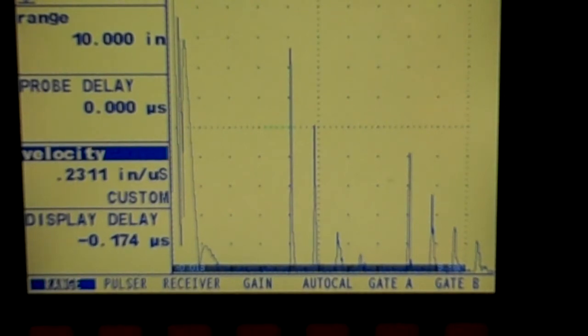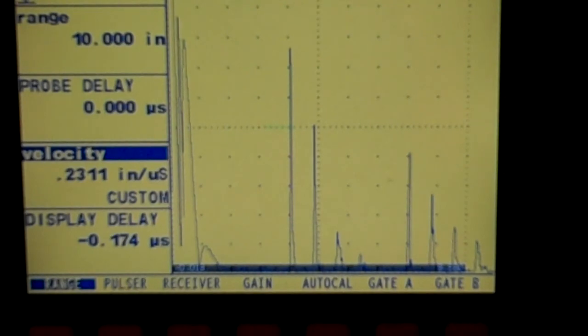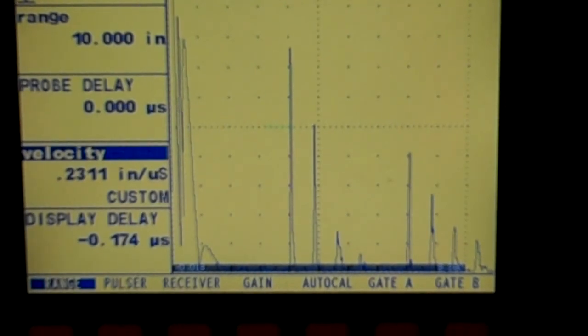Anyway, first lab done. Just testing a 10 inch range. We just set up a 10 inch range to make sure that our screen was calibrated, which it is. We know that the block is 1 inch thick. We had our 10 divisions across the screen, so that should make it a little bit easier.